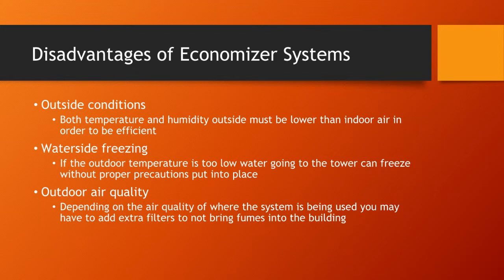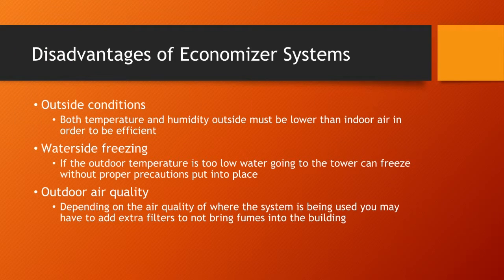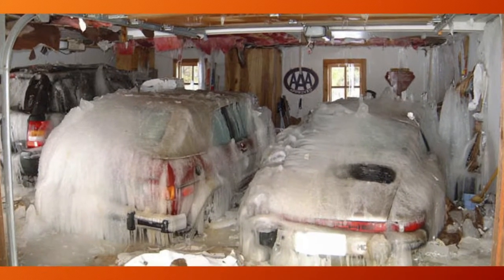So some disadvantages to an economizer system is the outdoor conditions. Depending on where you're at in the country, it might not make sense to use outdoor air because of the humidity. Another thing for a water side is you have to worry about freezing from pipes going to your tower and going back in the building. They can rupture when they freeze, crack, you have to worry about leaks, and you can flood out your building. So there's a lot of money involved if something like that would happen.